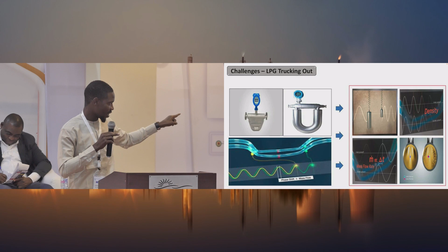You have to. Because LPG is not like white product. You can dip white product and have the same quantity today, come in later and have virtually almost the same quantity. LPG, you can see 2,000 metric ton now, come later in the night, you see 2,050. 50 metric ton from where? And then you can also see 1,950. So you can't use what is in the tank to convince the auditor or whoever comes to you. You can't use it. So they only rely on the flow meters and the mass totalizers. So this is an issue, but we found a way around it. Next slide.